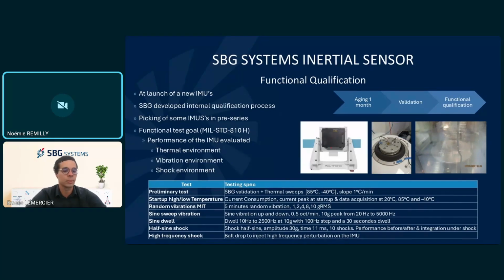First, we do startup at high and low temperature to evaluate the capacity of our IMUs to start at 85 degrees C or minus 40 degrees C and to behave normally. Then we also evaluate what the performances of our system will be in vibration. So we want to characterize the error of a sensor with a vibration from 1 GRMS to 10 GRMS.